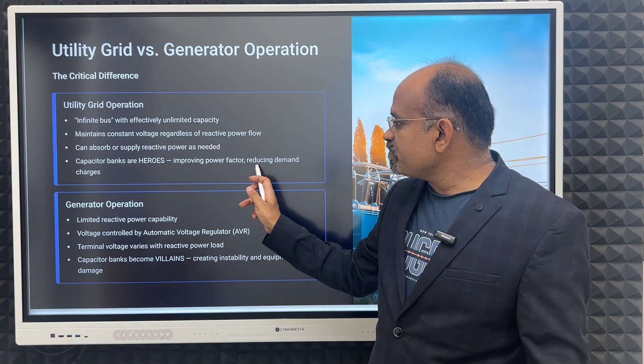What are we doing? Improving power factor in the case of utility grid operation. Now, what happens during generator operation? Reactive power capacity is limited. Voltage is controlled by the automatic voltage regulator, AVR. We have seen in the AVR module that voltage is regulated automatically. Then terminal voltage varies with reactive power load.